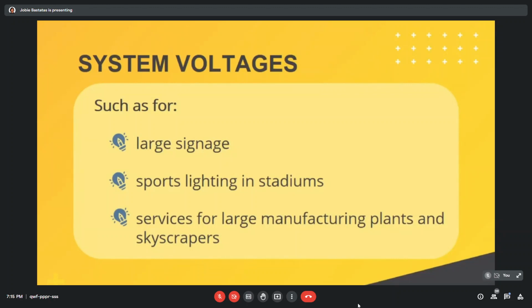So mostly we see the three-phase system in industrial and commercial installations because of the distance and the large power consumption. A three-phase system is an economical way of bulk power transmission over long distances and for distribution. Why do they use a three-phase system? Because it provides greater power density than a one-phase circuit at the same amperage, keeping wiring size and cost lower. In addition, three-phase power makes it easier to balance loads, minimizing harmonic currents and the need for large neutral wires.